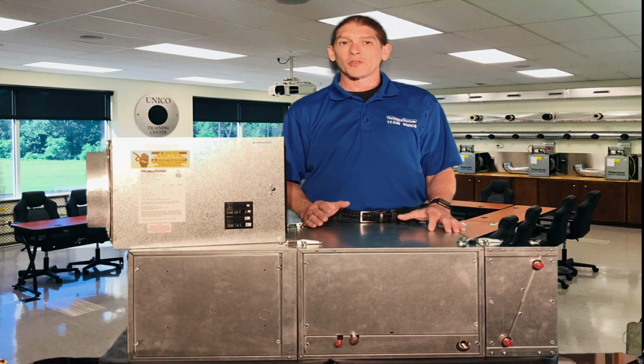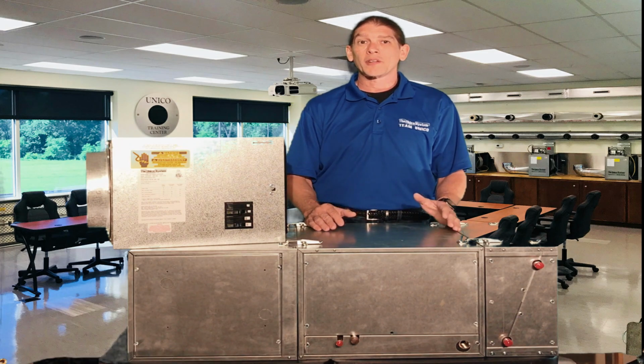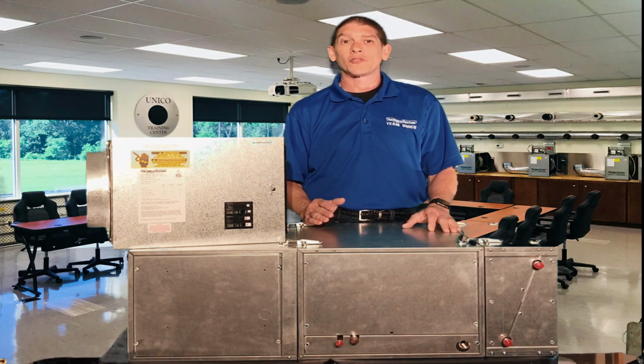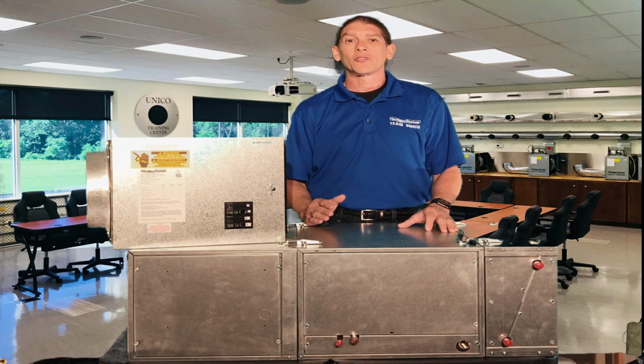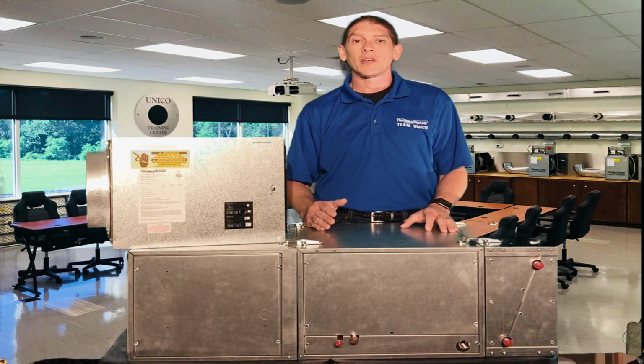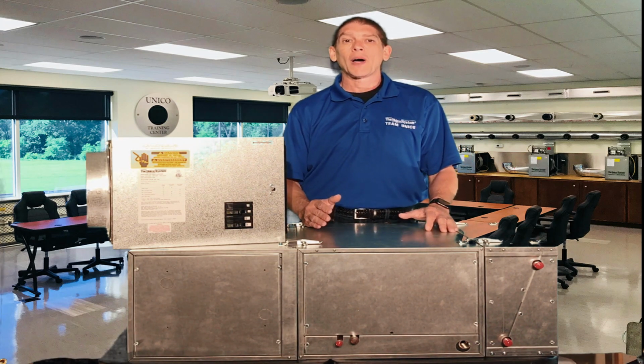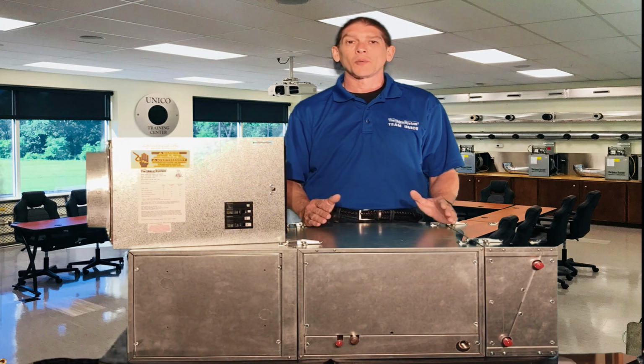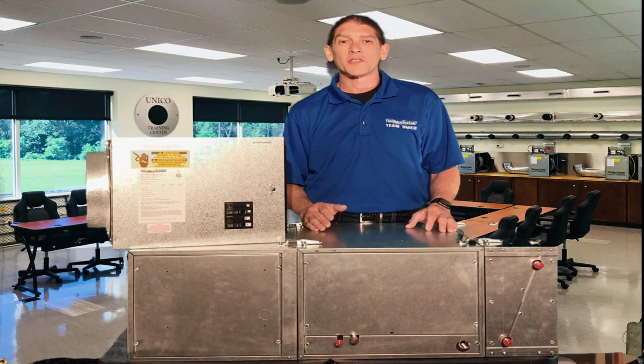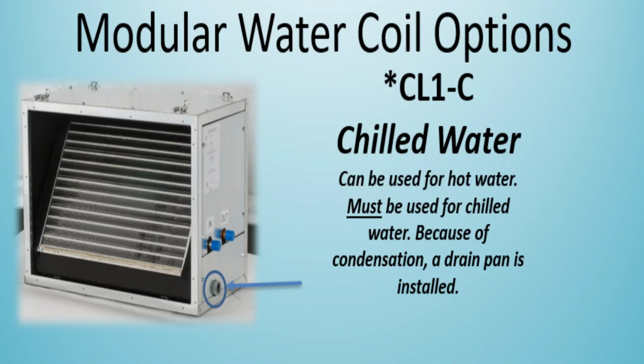We have two ways of doing that actually, either with a dedicated hot water coil, or if there's a chiller being used for cooling, we have a chilled water coil that will also take care of the heating. Just simply pipe in shutoff valves to isolate the boiler or the chiller depending on the season. Remember that the hot water coil strictly for hot water does not have a condensate drain.